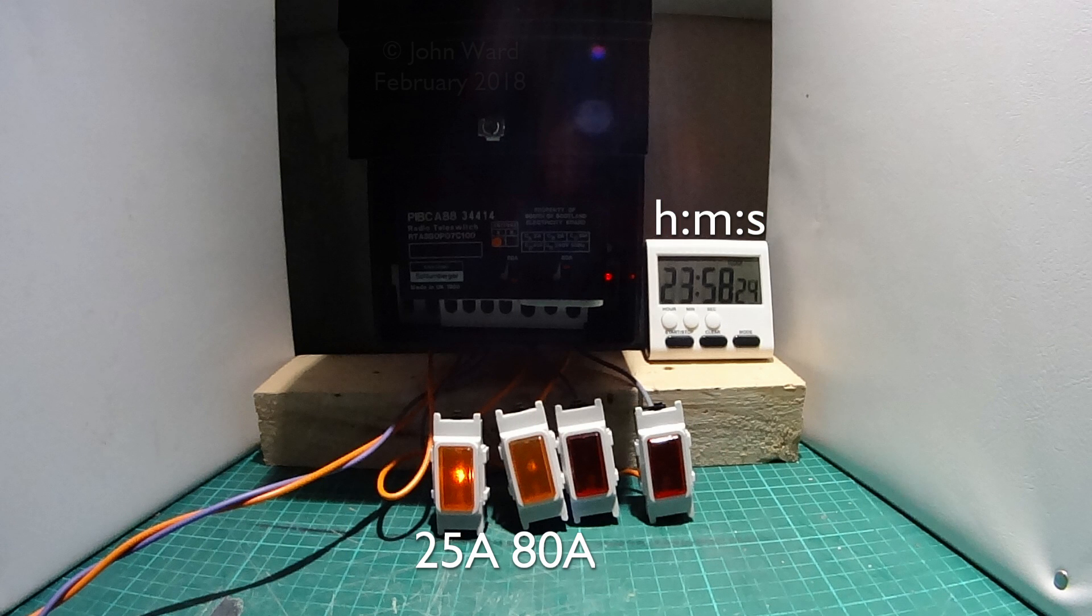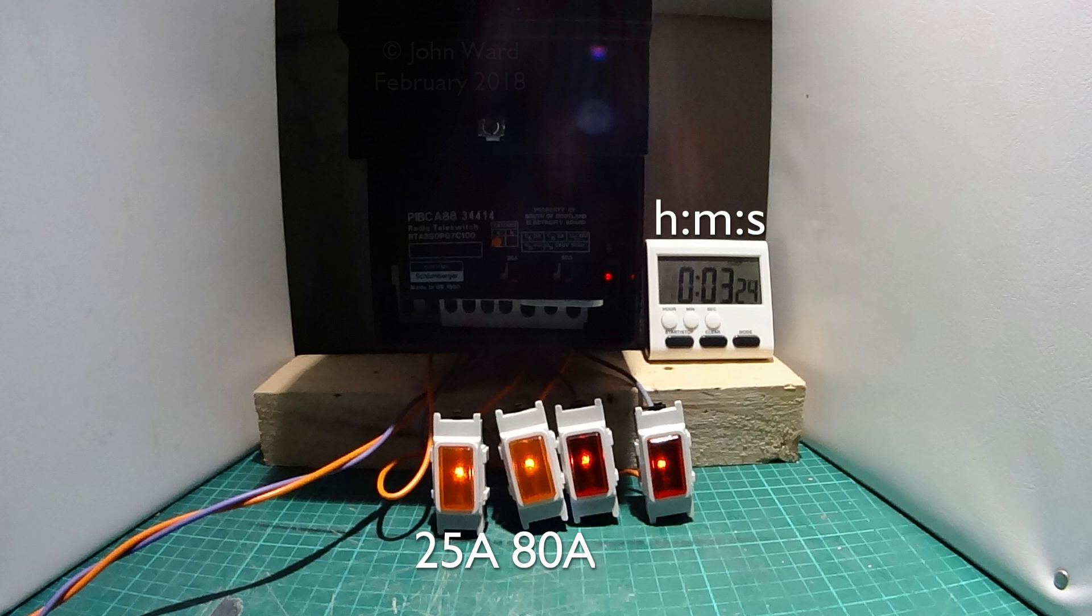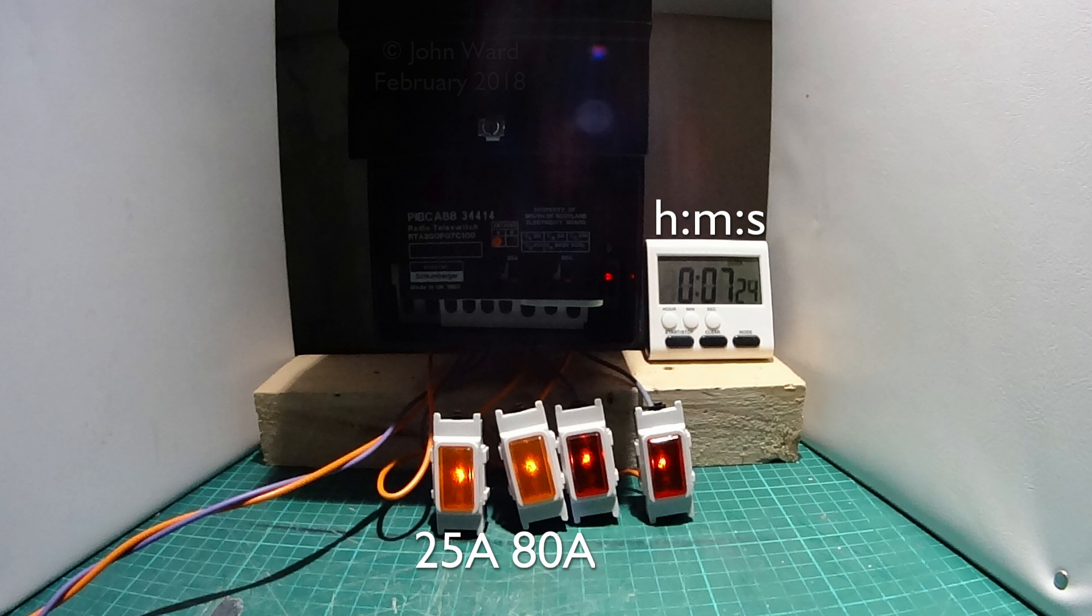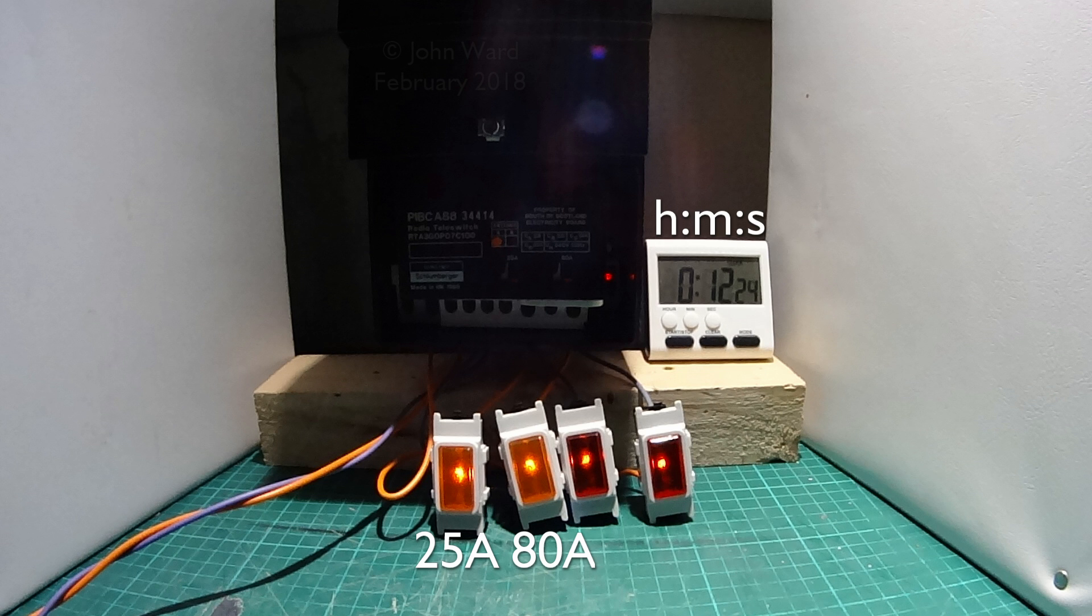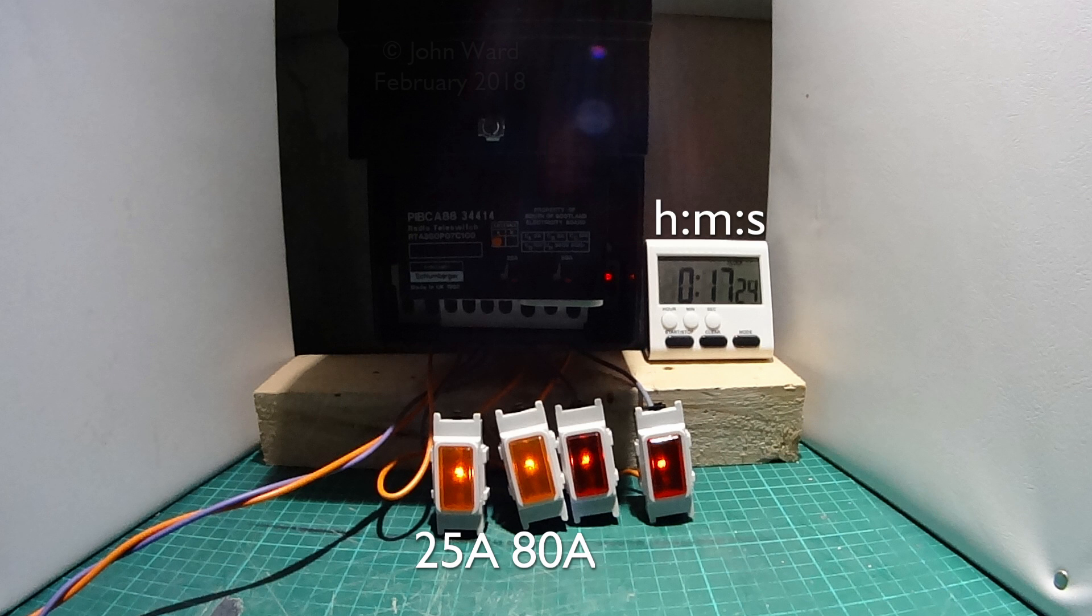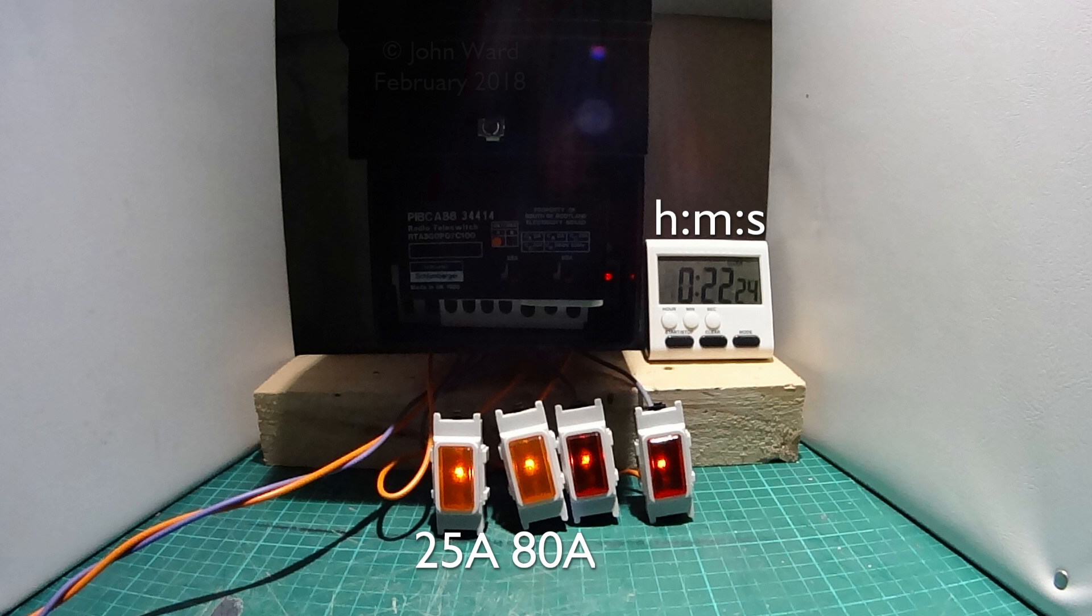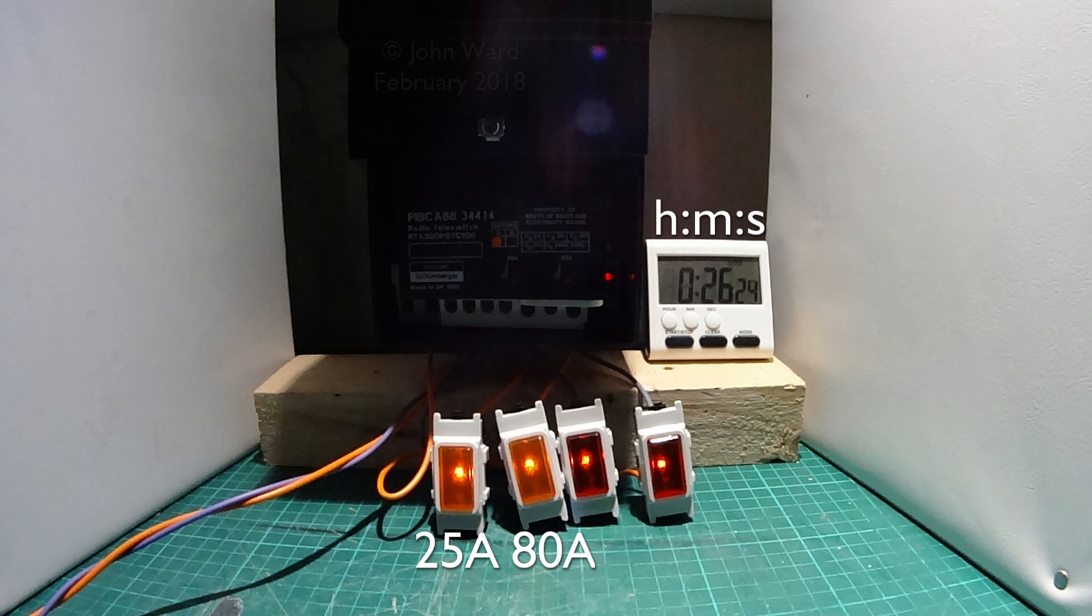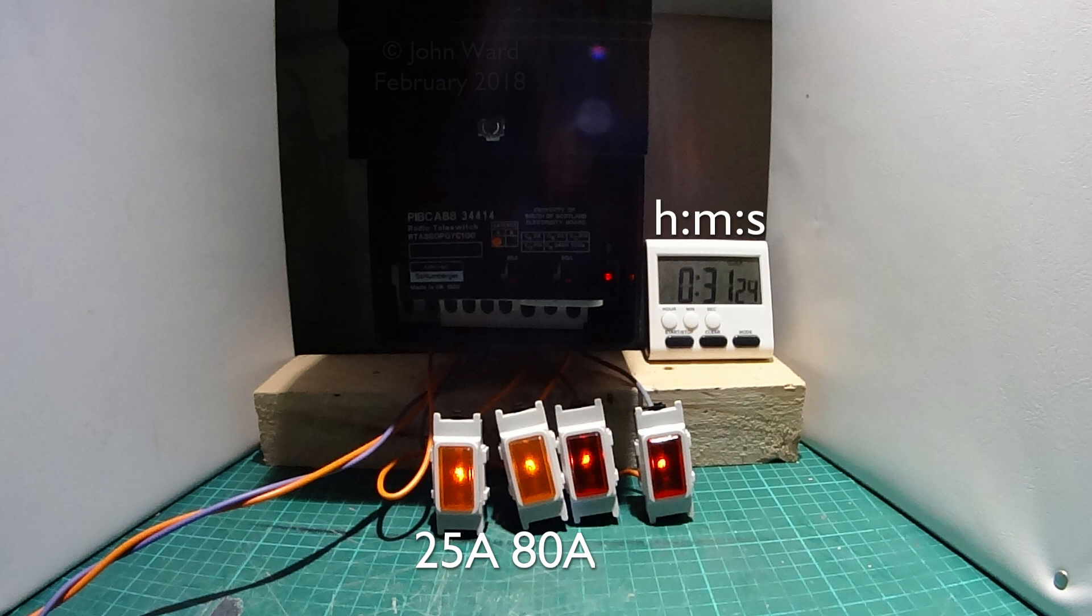So we're just coming into midnight here. And we should see just after midnight that all of the other three will switch on there. And so now we've got the hot water on, which is the left orange one. The storage heaters, which is the second orange one. And also got both of the red indicators on, which are the rate-changing ones. So essentially all this power now is going to be used at the lower and cheaper rate. And that's kind of what we wanted, because that's the whole point of this system in the first place, for the householder, in that obviously it's cheaper to use on this particular system.